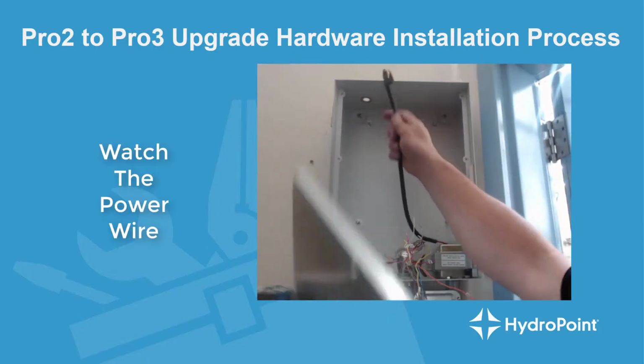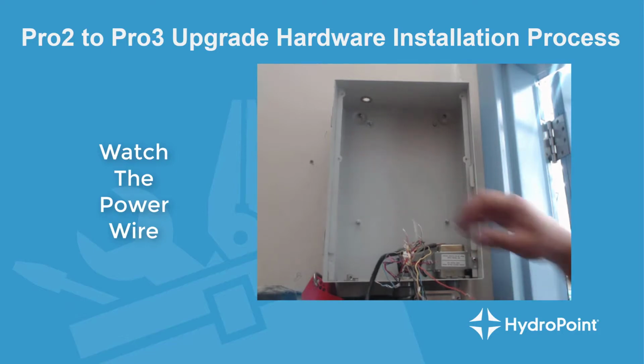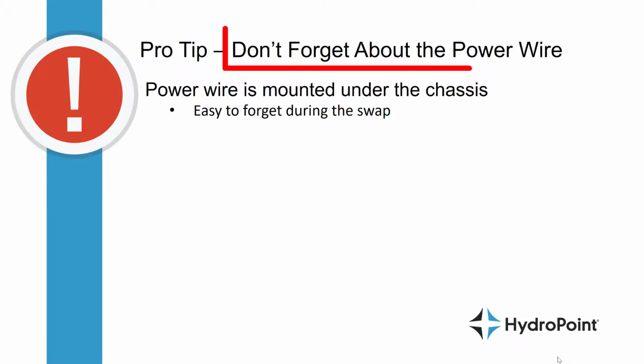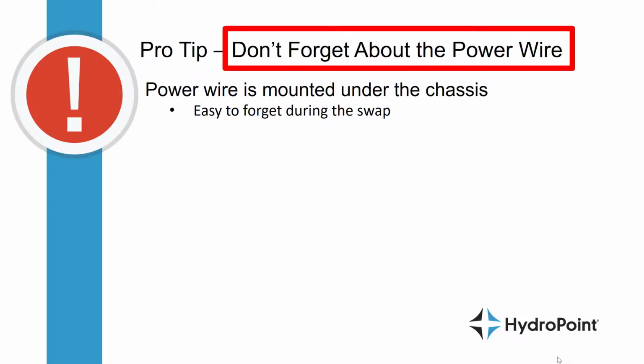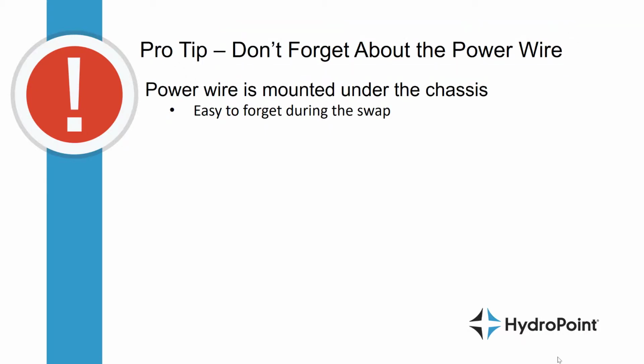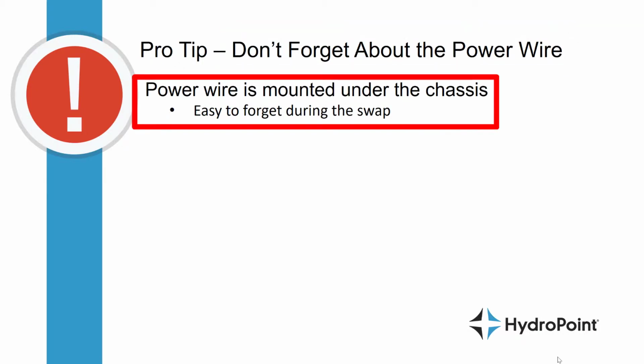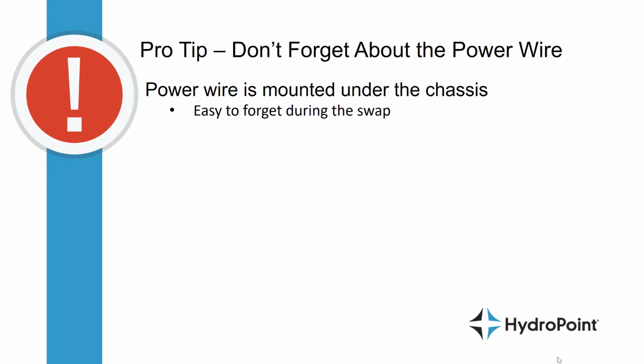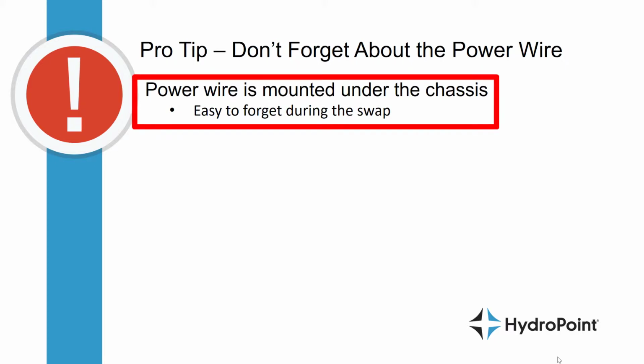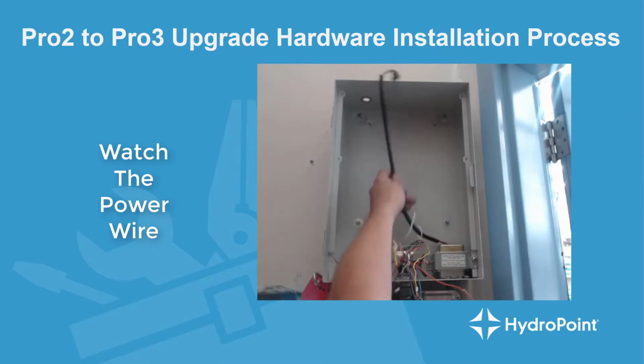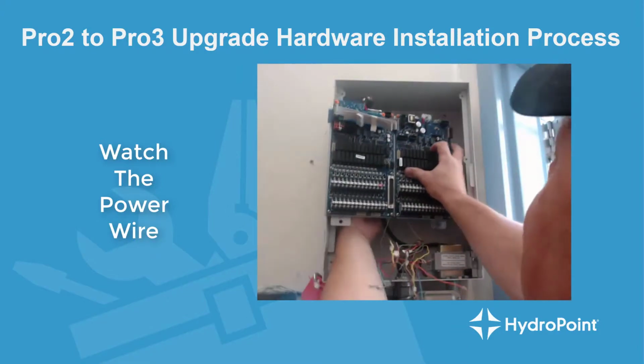Then you remove the chassis from the enclosure, paying special attention to the wire that comes from the transformer. Because we don't use it for a while, it's easy to forget that power wire is mounted underneath the chassis. But if you forget until everything else is plugged in, everything will need to be uninstalled so we can lift the chassis up to run that power wire underneath. It can cost you a lot of time, so pay special attention to run the power wire right up the middle of the chassis.